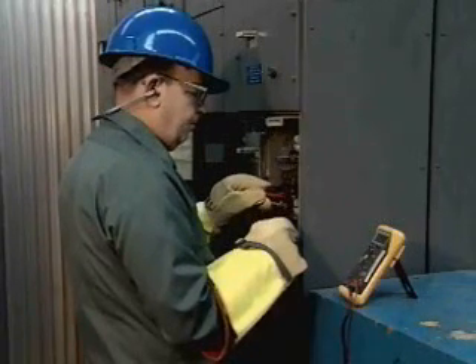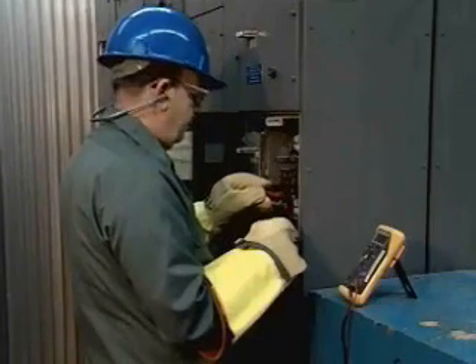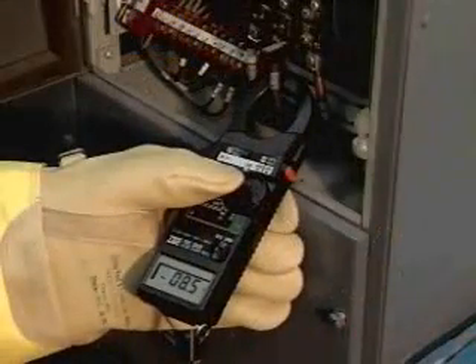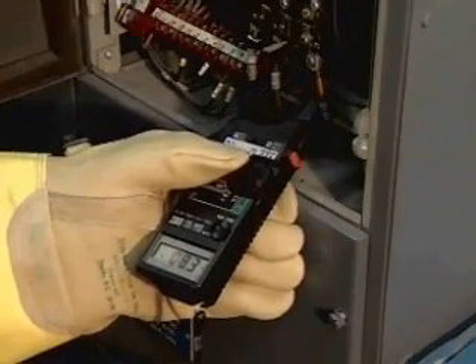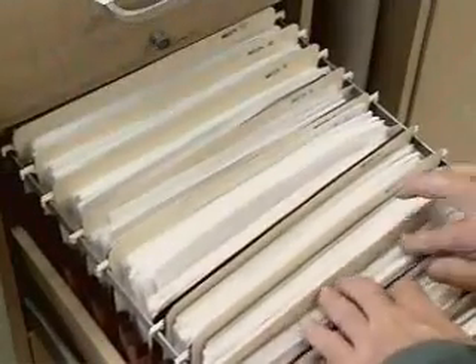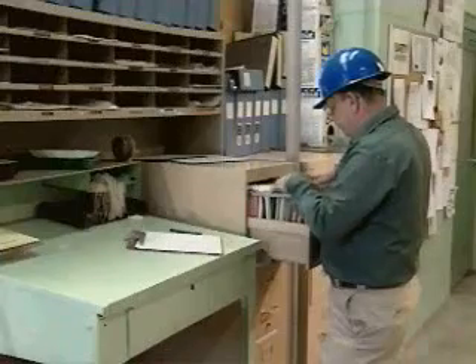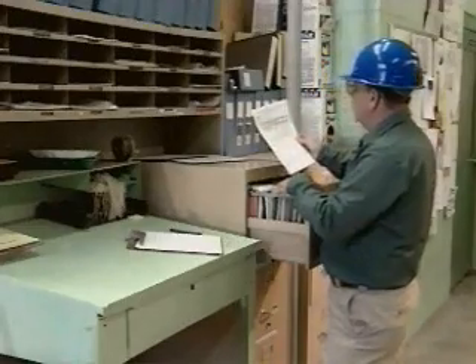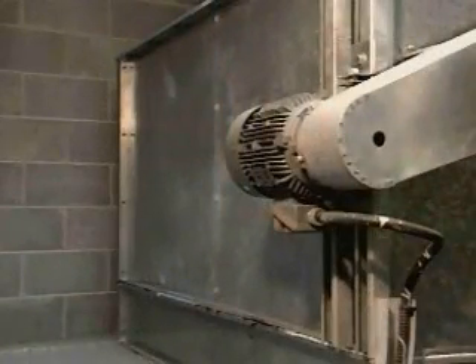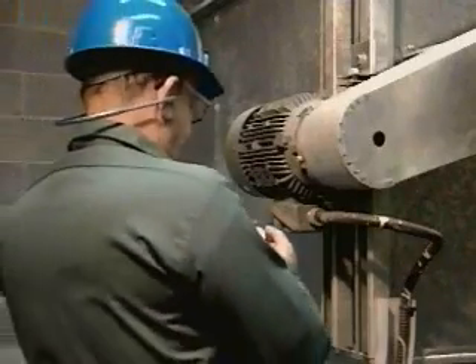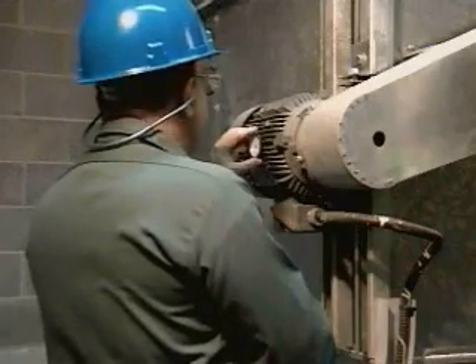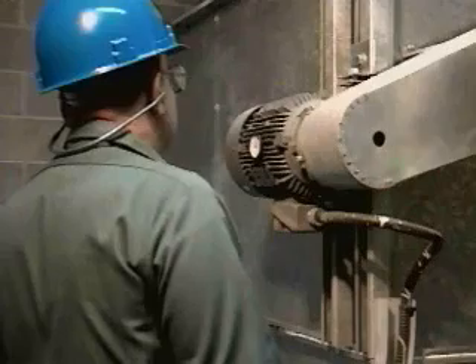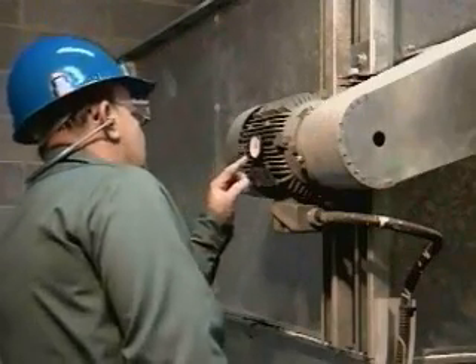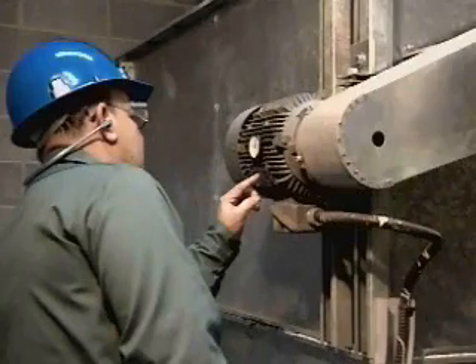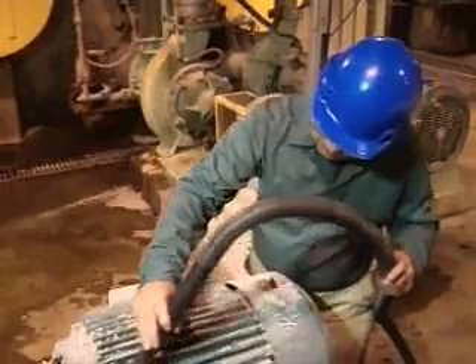Another critical part of a preventive maintenance program is measurement. Measurement allows you to accurately assess the functioning of various aspects of the motor. These aspects include current, temperature, and vibration. To determine if your equipment is functioning properly, it is not enough to take measurements alone. When you take measurements, you must compare them to previous measurements in order to track equipment performance. Over a period of time, measurement records will indicate if trends exist in the functioning of the motor. Such trends can reflect a gradual deterioration in a specific area of the motor. In order to make accurate comparisons, measurements must be taken in the same place time after time. Select Next to continue.